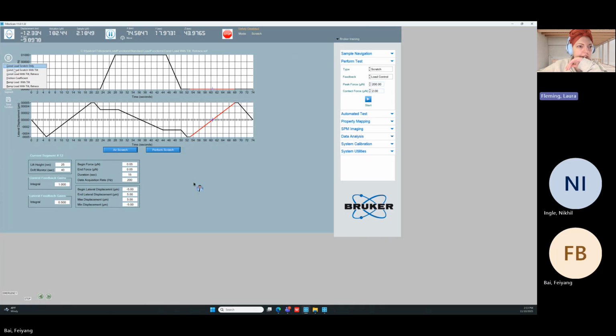Okay. And then we get into, so basically, I showed you this one, constant load scratch. Never do this one. You always want to be able to correct your sample tilt. So typically I don't recommend you use that one. Instead, I recommend you use either constant load scratch with tilt or with tilt and retrace, depending on what information you want from the rest of the test.